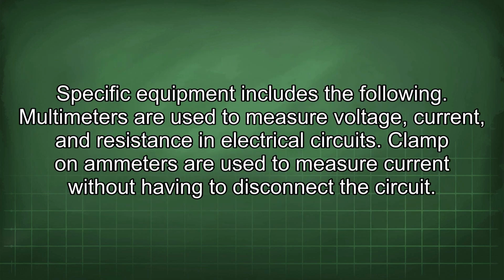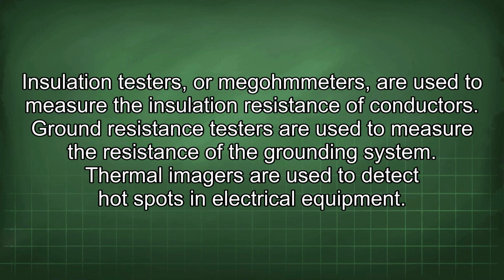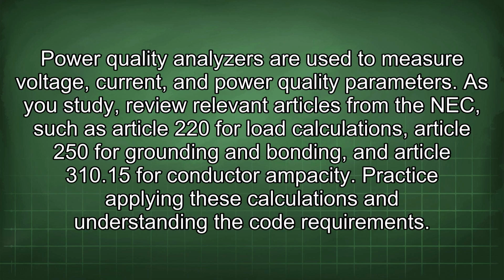Specific equipment includes the following. Multimeters are used to measure voltage, current, and resistance in electrical circuits. Clamp ammeters are used to measure current without having to disconnect the circuit. Insulation testers, or megohmmeters, are used to measure the insulation resistance of conductors. Ground resistance testers are used to measure the resistance of the grounding system. Thermal imagers are used to detect hot spots in electrical equipment. Power quality analyzers are used to measure voltage, current, and power quality parameters.